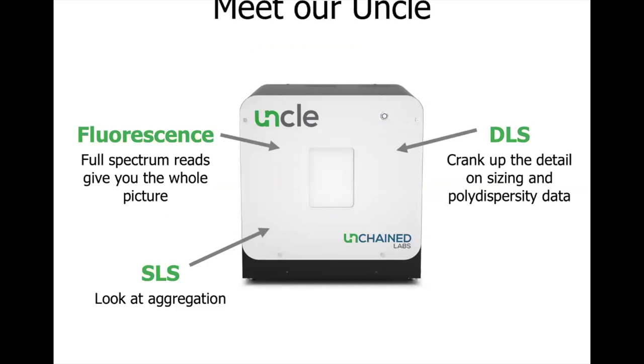Let me first introduce you to our UNCLE. UNCLE is a multimodal biologic stability platform that combines three detection methods: fluorescence, static light scattering (SLS), and dynamic light scattering (DLS). UNCLE can measure the full spectrum fluorescence from 250 nm to 720 nm to look at both the intrinsic fluorescence of tryptophan and tyrosine and the fluorescence of protein dyes.